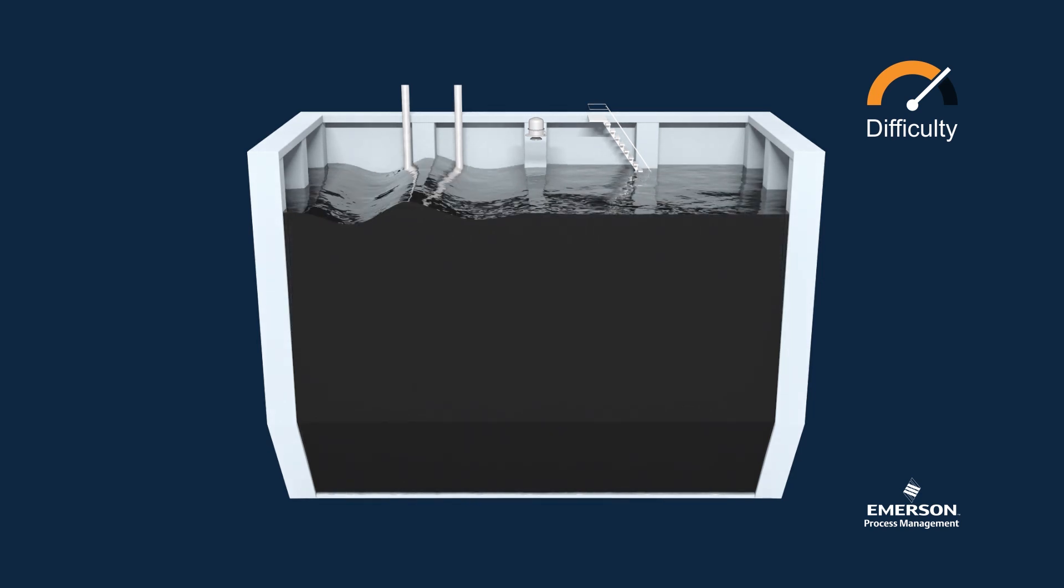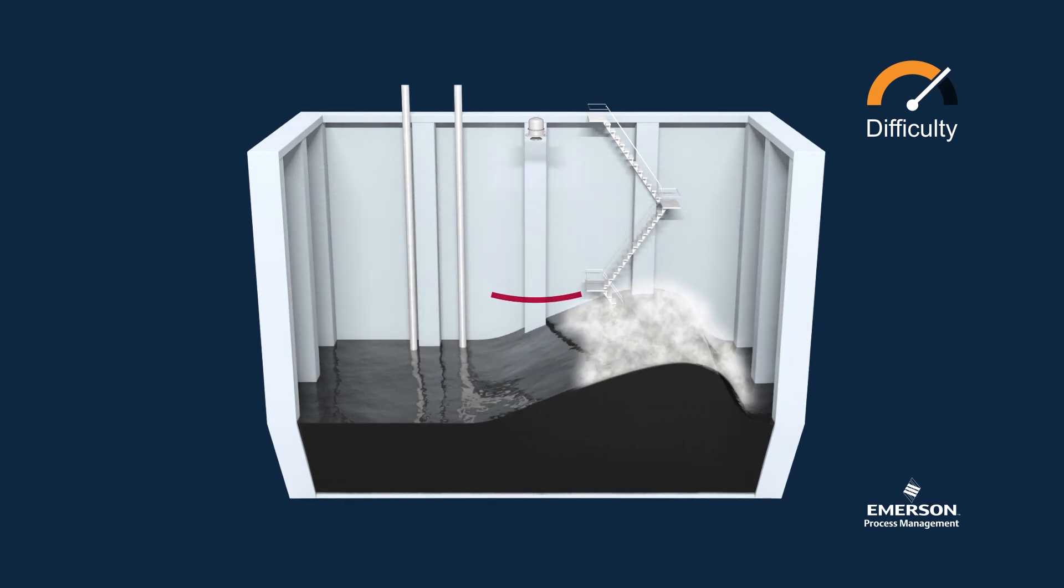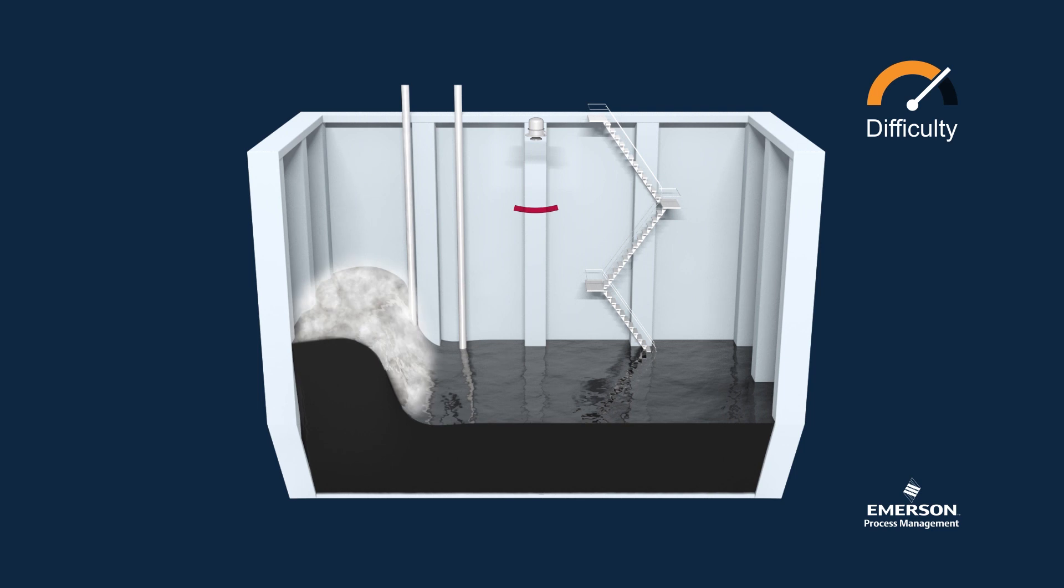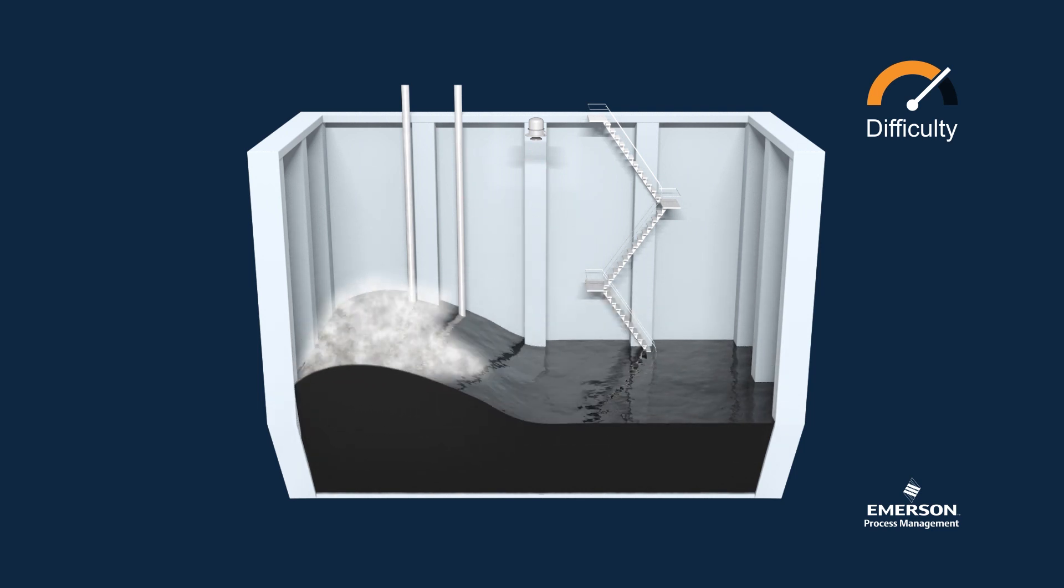When the ship rolls and pitches in the ocean or even from heavy seas, waves of several meters height can roll back and forth in a tank, making the radar emitted energy bounce off the waves in unwanted directions, reducing the returned echo strength and moving the liquid level.